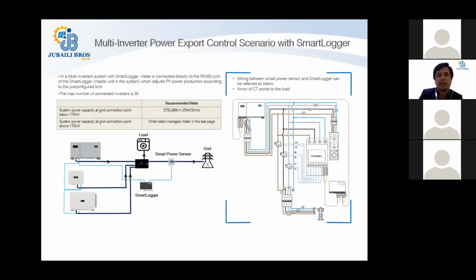Multiple inverter power export control scenario with a Smart Logger. Now, when you have a Smart Logger in your system and you have multiple inverters, the connection of the smart power sensor or the third-party power meter is made to the Smart Logger. The Smart Logger reads the data from the power meter, applies the logic, and then sends the command to the inverters to have the necessary control done as per the active power control that you will require, which we will be speaking about in detail.